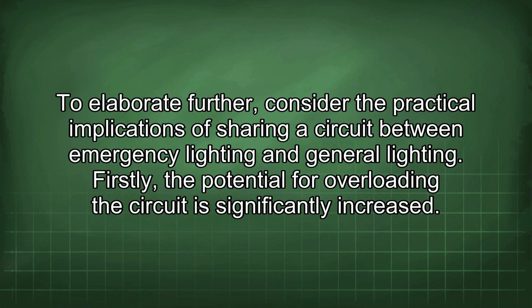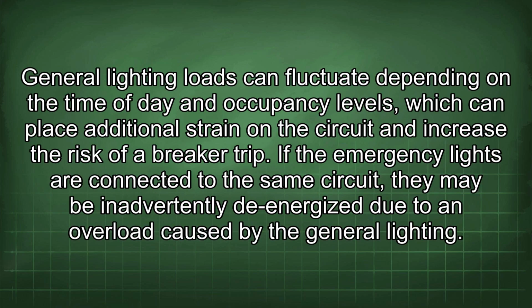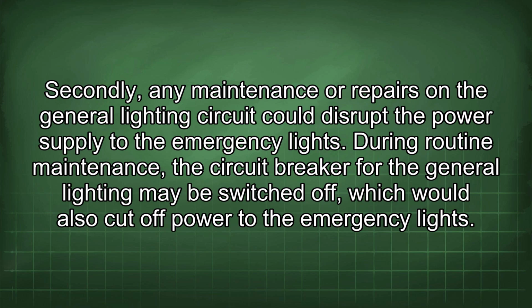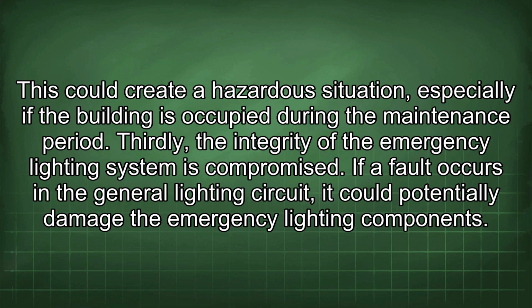To elaborate further, consider the practical implications of sharing a circuit between emergency lighting and general lighting. Firstly, the potential for overloading the circuit is significantly increased. General lighting loads can fluctuate depending on the time of day and occupancy levels, which can place additional strain on the circuit and increase the risk of a breaker trip. If the emergency lights are connected to the same circuit, they may be inadvertently de-energized due to an overload caused by the general lighting. Secondly, any maintenance or repairs on the general lighting circuit could disrupt the power supply to the emergency lights. During routine maintenance, the circuit breaker for the general lighting may be switched off, which would also cut off power to the emergency lights. This could create a hazardous situation, especially if the building is occupied during the maintenance period.